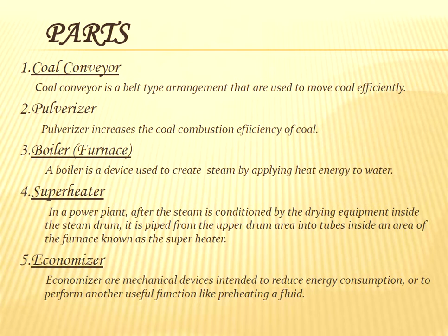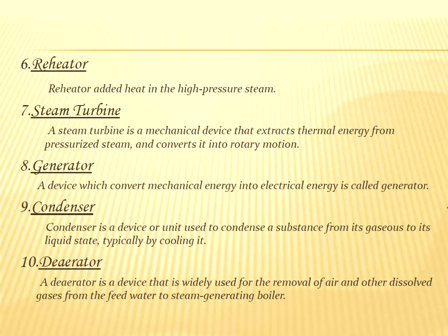so that it can run the turbine. Then we have the economizer which heats the incoming water using the waste heat which goes out with the smoke. Then we have the reheater, where the steam is heated between two turbines. Then we have the steam turbine.